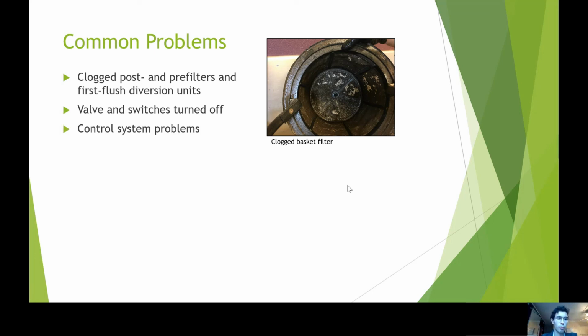And there have been, as I mentioned before, problems with the control systems. If the piece of equipment that provides input to the control system is no longer working, then the control system isn't reading the input correctly and outputs a wrong signal. Or perhaps the piece of equipment that it's supposed to output to is not reading the right kind of signal, and then the system is not going to work very well. Or in a case like this, it includes building management systems that don't have the correct communication protocol to communicate with the facilities building management system, or the contractors and suppliers of the building management system have since left, and there's no way to get the information that these systems have been collecting.